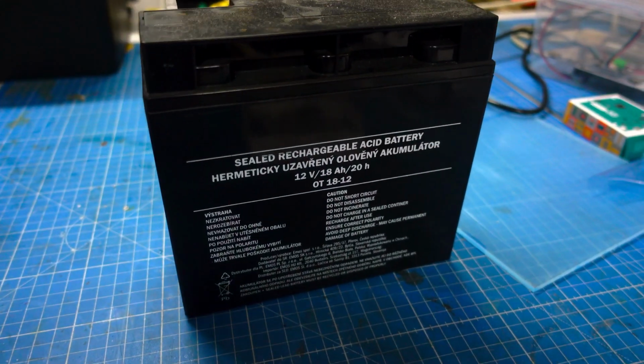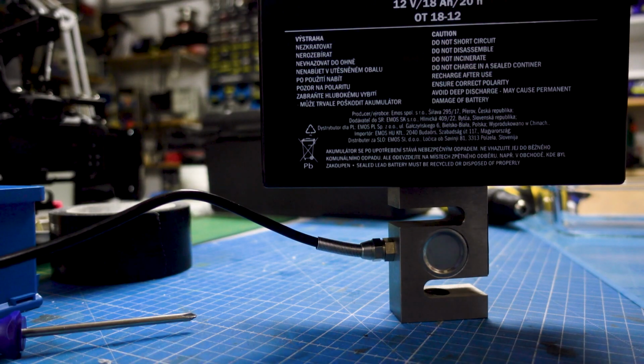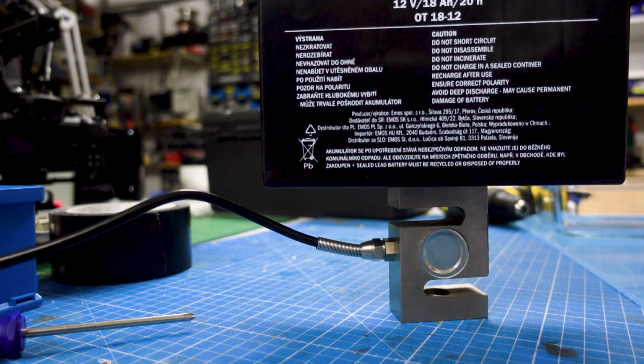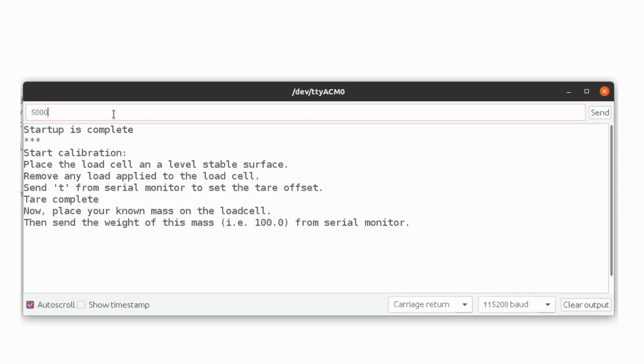In my case, because I have a 20-ton press and a 2-ton load cell, the bigger the weight that I put on there, the better it would be for calibration. So if I put on like 100 grams on there, that would be suitable for calibrating a 1 kilo load cell, but it doesn't make any dent for a 2-ton load cell. So I have weighed a motorcycle battery. This has pretty much exact 5 kilograms. So I use that as my calibration weight.